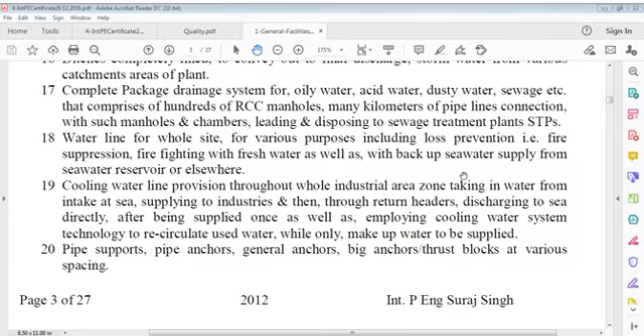Cooling water line provisions throughout the whole industrial area zone, taking in water from intake at sea, supplying to industries, and then through return headers discharging to sea directly after being supplied once, as well as employing cooling water system technology to recirculate used water while only makeup water is supplied.